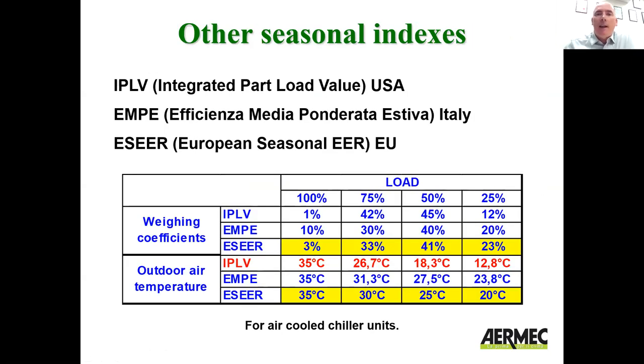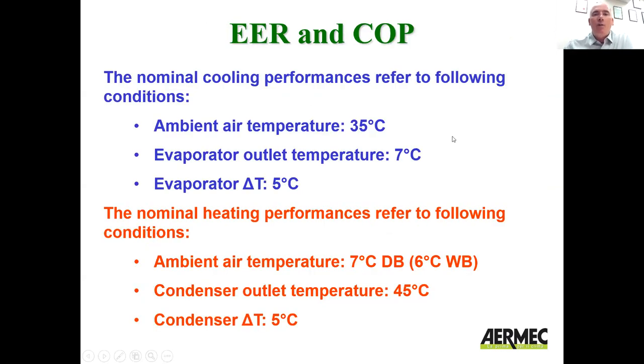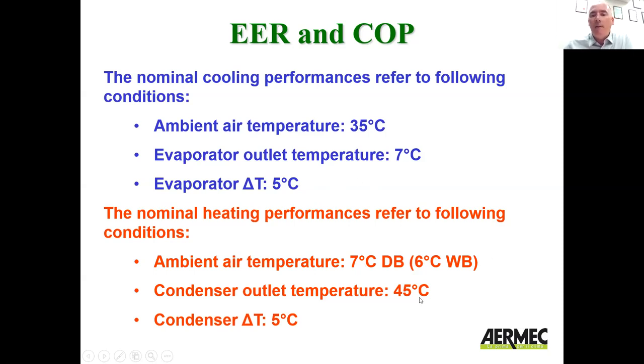If you have a client that's not European — perhaps American — they may look for the IPLV unit of measurement. It's a similar formula but just a slightly different variation. The criteria they ask for is supply 7°C, return 12°C, which is a 5-degree delta C, at an ambient of 35°C — because remember, they're testing for all of Europe, so everyone has to supply data at the same conditions. If it's a heat pump, they will use a dry bulb ambient of 7°C, with a supply of 45°C and a return of 40°C, again using your 5-degree delta C.